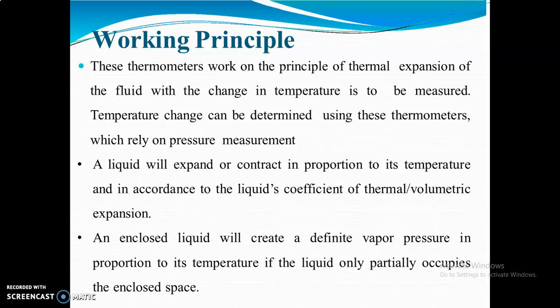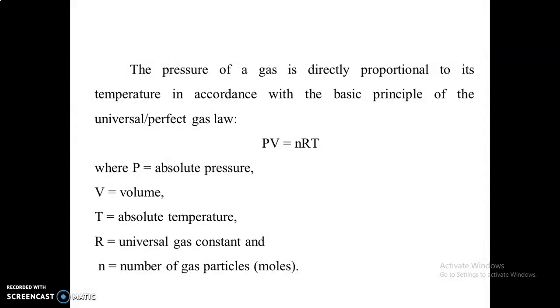For pressure measurement, we use the Bourdon tube. The liquid will expand or contract in proportion to its temperature in accordance with the coefficient of thermal expansion. An enclosed liquid will create a definite vapor pressure in proportion to temperature, if the liquid only partially occupies the enclosed space. The pressure of the gas is directly proportional to temperature. The basic principle is the gas law: PV = nRT, where P is absolute pressure, V is volume, T is absolute temperature, R is the universal gas constant, and n is the number of gas particles.